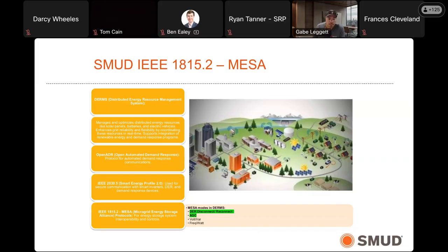With MESA 1815.2, especially in DERMS, at a minimum it's going to be DER disconnect and reconnect, and automatic generator control. With AGC, our DERMS runs an algorithm based on input data to determine the best time to send a fleet-wide charge and discharge command. The battery system accepts that signal, changes its active power target based on the DERMS output, and also runs local volt-var or frequency-watt control to help with grid stability.